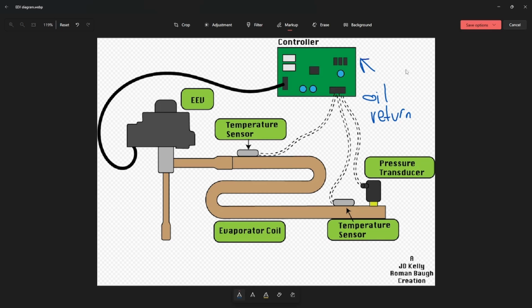It runs that through its algorithms to know a general idea of how much oil is left in our compressor. When that algorithm senses that the oil level is low, based on its algorithm, not on a sensor, strictly based off of runtime, when that board sees that the runtime and the run speed, as it calculates it, has low oil reserves left in the compressor, it will actually shut down a cooling call and run into its oil return mode to pull the oil back to the compressor so that it doesn't damage it. Once the oil return mode is complete, it will resume normal operation.